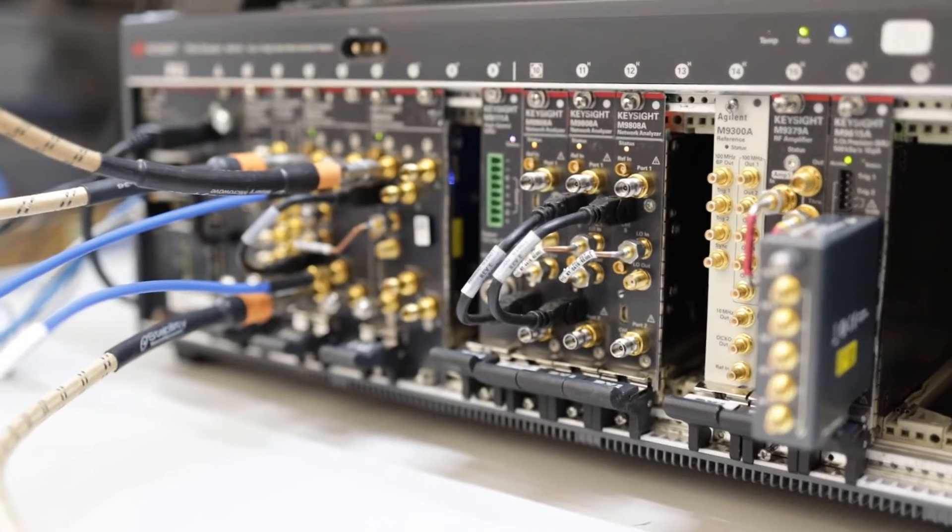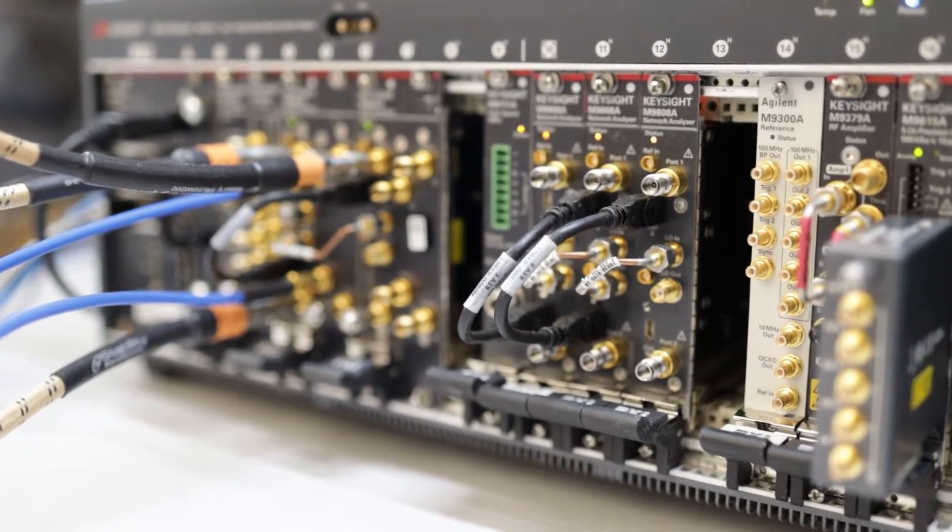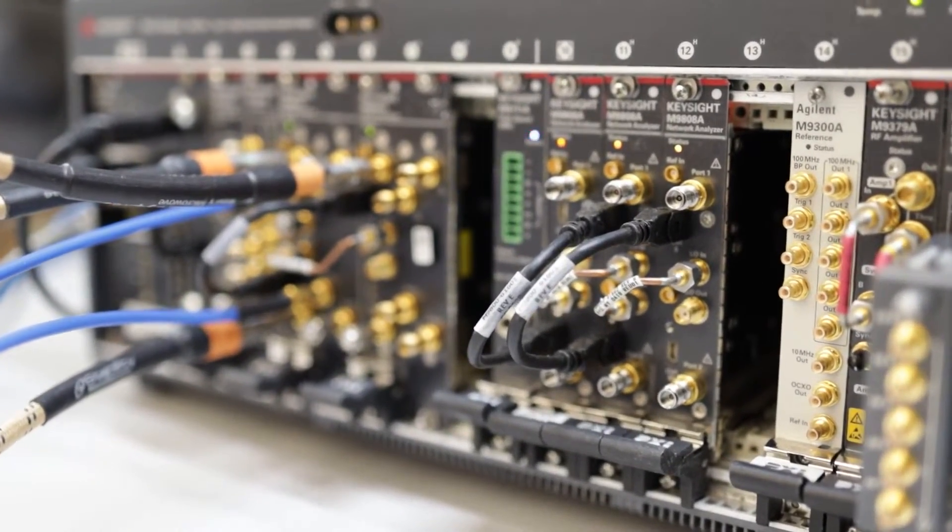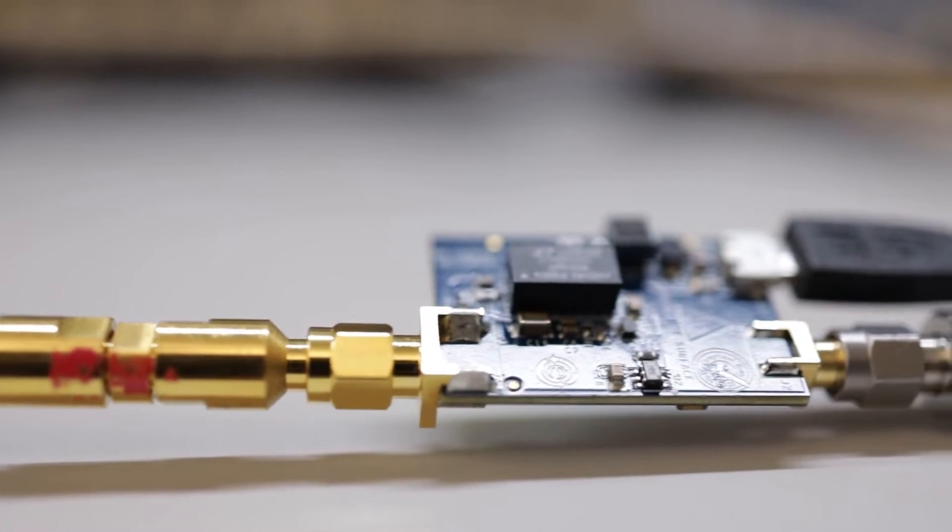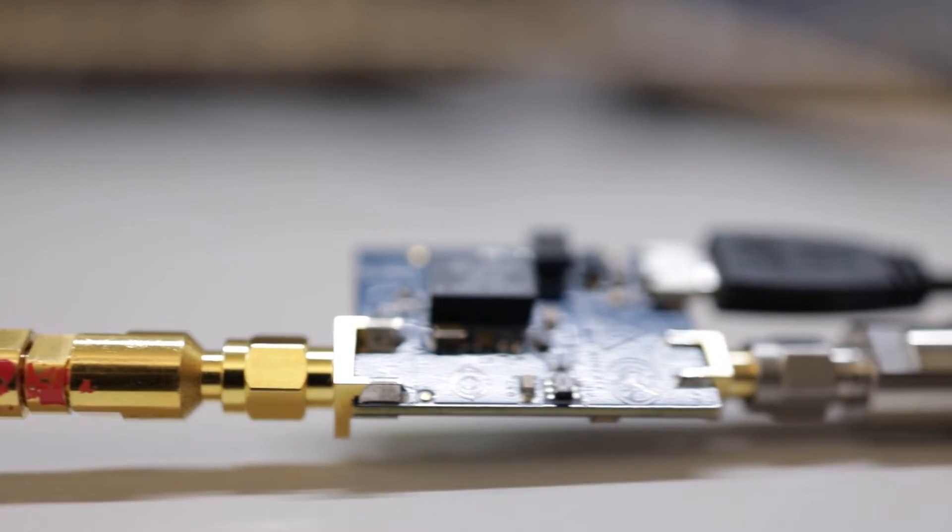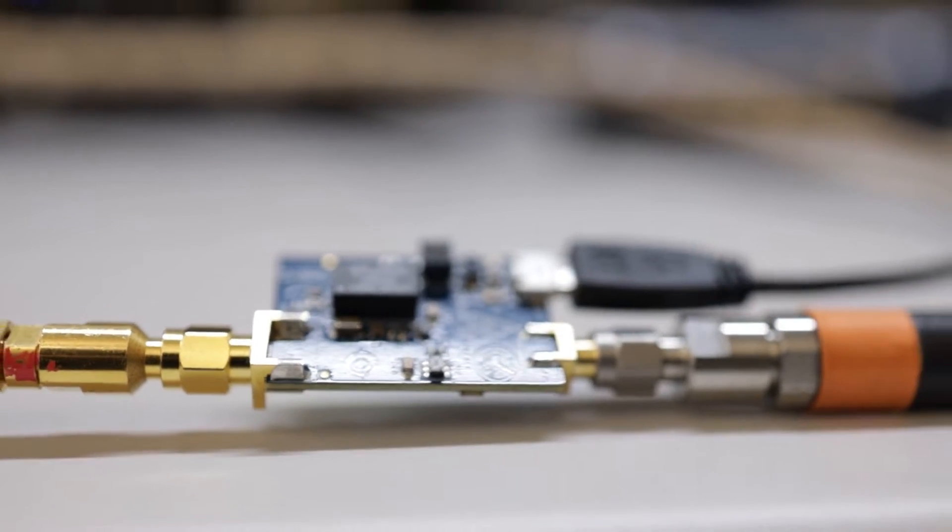The Pixi VNAs or PXIs allow for multi-port complex configurations. So the swept IMD application is used for testing amplifiers and converters, and these amplifiers and converters can be components or they can be part of a larger system used in TR modules or satellite tests in different systems.